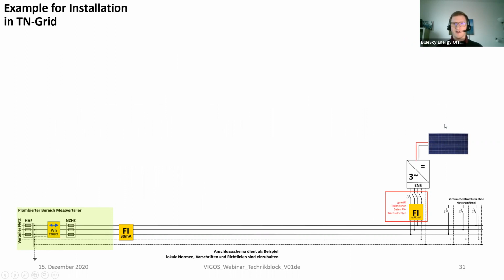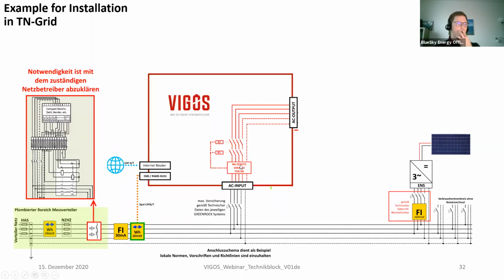In here you see an already installed PV AC inverter. So that's like an SMA, Fronius, or SolarEdge, whatever you're used to. And we also have a few load connections, so your house installation. And here we now add a Vigos system, for example. So we just connect it to the distribution panel like we would do with an inverter or a load. But what is really important is that you place an energy meter directly at the grid input point. This energy meter makes sure that the system charges and discharges with the correct power according to the excess or to the energy coming from the grid. So that's really an important point, that this energy meter is placed directly at the grid input point.